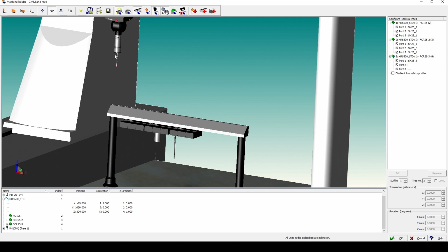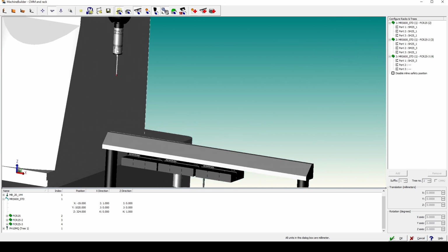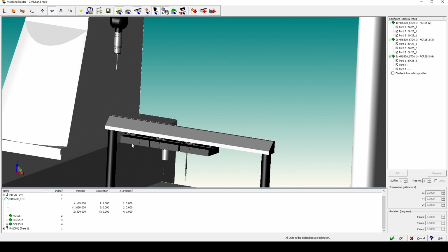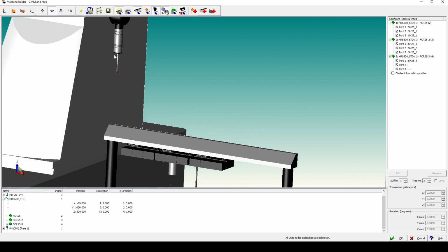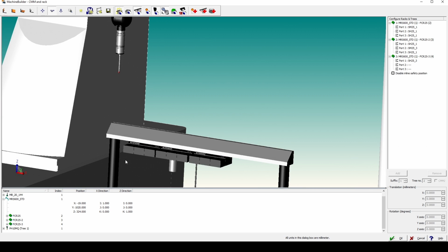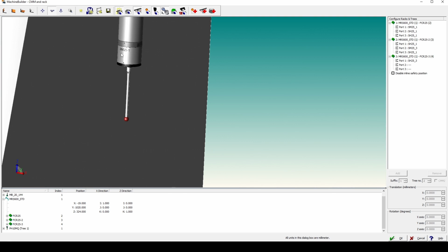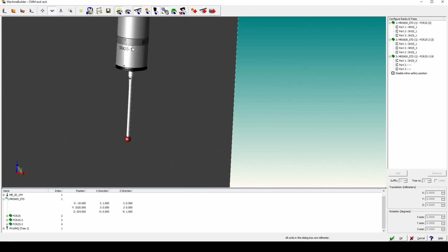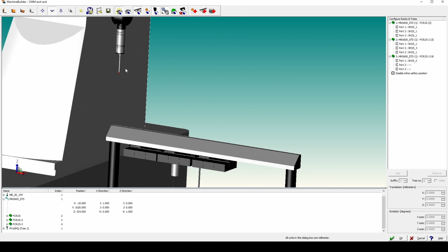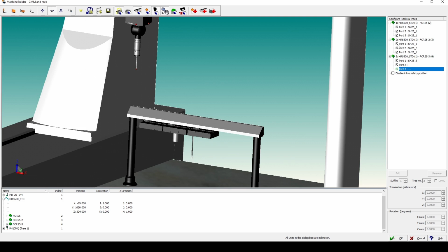So now, if you think to change probe 1 to probe number 2, you have to drop SH25 somewhere, but you cannot drop it in the same position as probe 1 sits, because it's configured to sit with SM25-1. So we have to use some parking position, and we're going to use port 3 for parking.